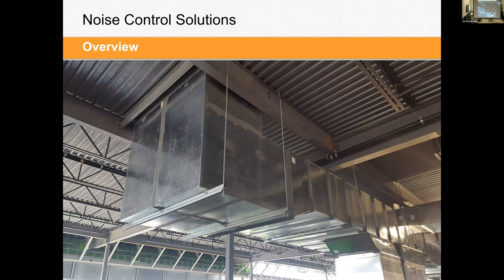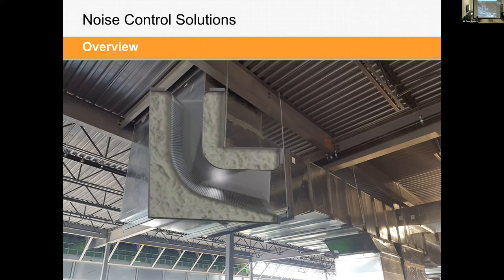You can see the drop through the roof deck into the following ductwork here. A great place to attenuate the noise is as close to the source as possible, while considering your inlet and outlet conditions and system effects. Attenuating the noise right here is a great option because, if you look downstream, there are a lot of tees, junctions and takeoffs that would transmit all of that noise into the facility. That would be where that elbow is.